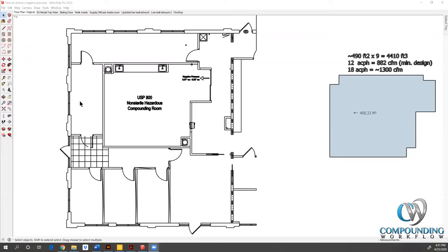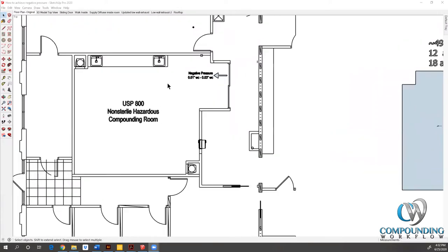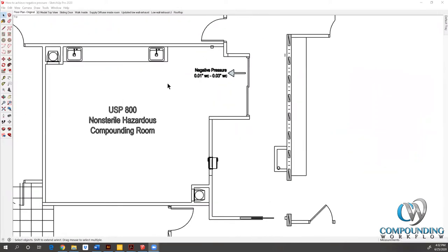I thought this would be a great project to show you how to achieve negative pressure. What we're looking at here is a floor plan, a very standard two-dimensional floor plan. This room right here in the middle is going to be our USP 800 non-sterile hazardous compounding room. Coming in through the sliding doors here, we've got it at negative pressure 0.01 inches of water column to 0.03 inches of water column.